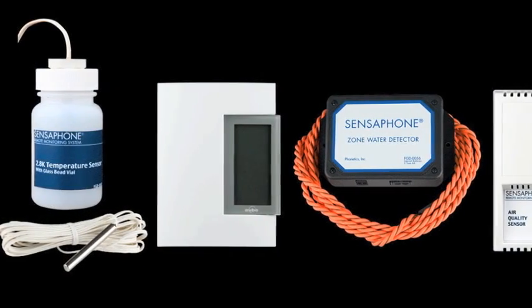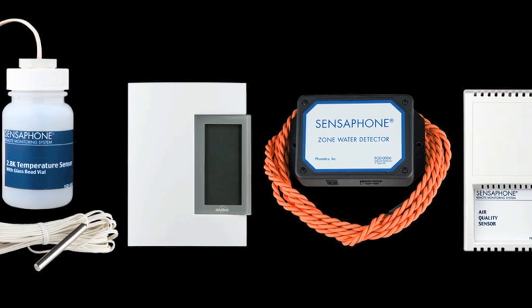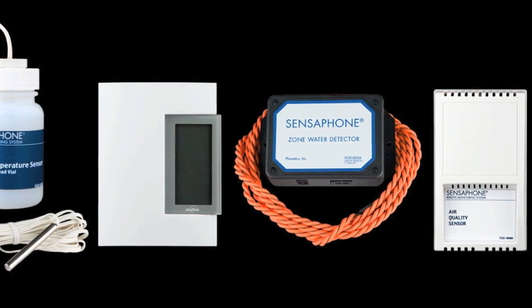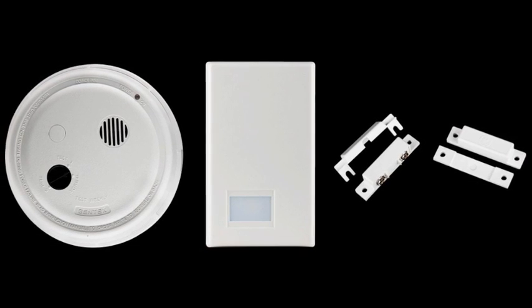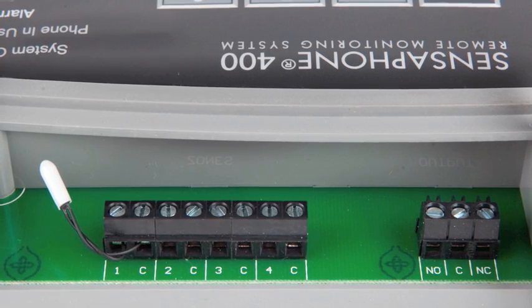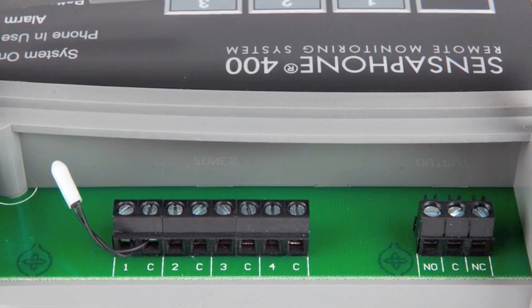Sensaphone makes a full line of sensors which can monitor for variations in temperature, humidity, air quality, and the presence of water or smoke. The 400 also accepts sensors that monitor for physical security such as motion detectors or contact switches. Each sensor zone can be configured for either dry contact or temperature, and a zone configured as a dry contact can be used with any normally open or normally closed device.